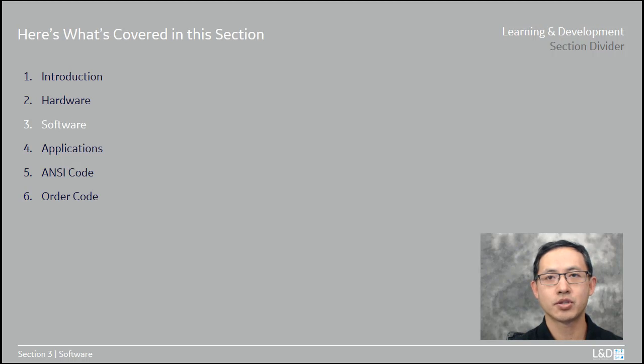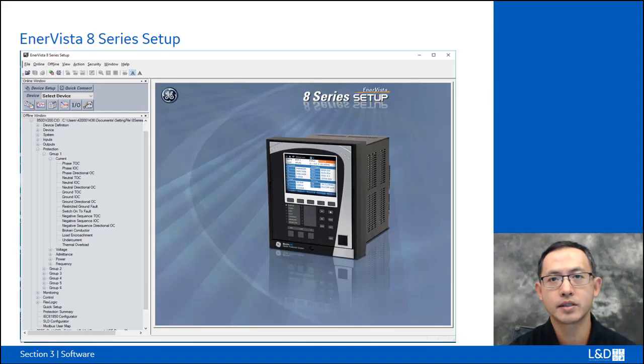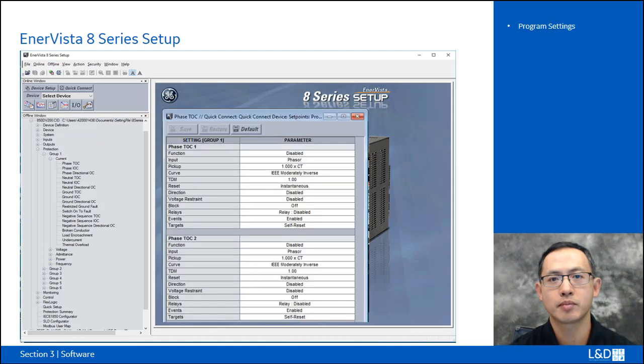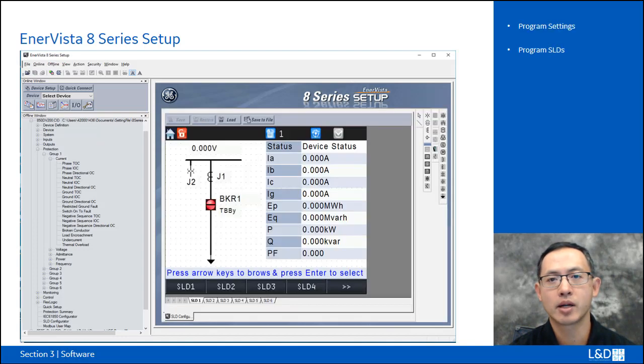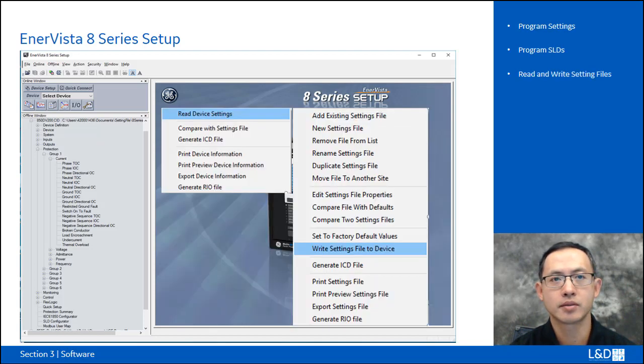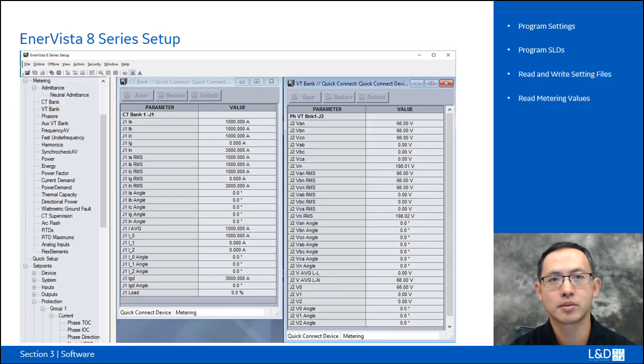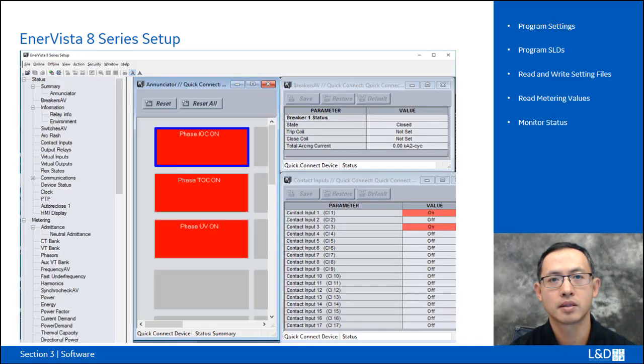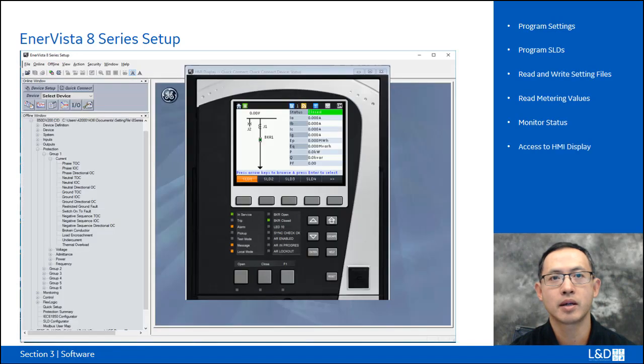In the software session, we're going to talk about the software interface and the setting files, also the graphic HMI interface. EnerVista 8 series setup software is one software that works with 4 types of 8 series relays. It can program the settings, single line diagrams, annunciator alarm, and time push buttons. It can read and write setting files, read metering values, monitor status, and access the HMI display.